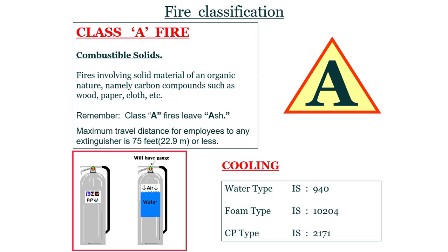Class A fire — combustible solids: fires involving solid material of an organic nature, carbon compounds such as wood, paper, cloth, etc. Remember, Class A fire leaves ash — when you burn wood or paper, you will get ash as a residue. Maximum travel distance for an employee to any extinguisher is 75 feet (22.9 meters) or less. For extinguishing Class A fire, cooling is the best method. Water type IS 940, foam type IS 10204, and DCP type IS 2171 are recommended.